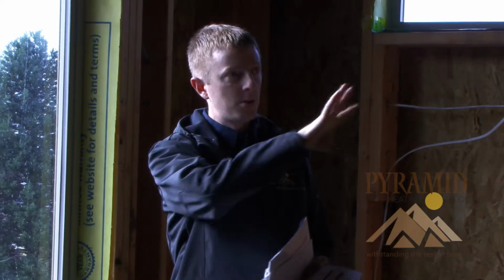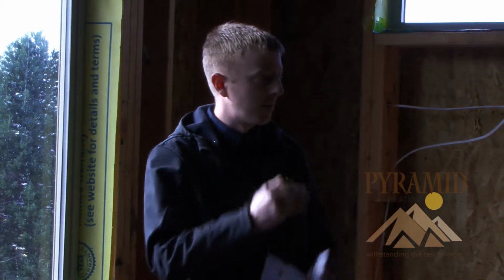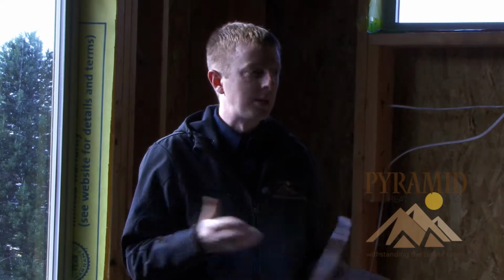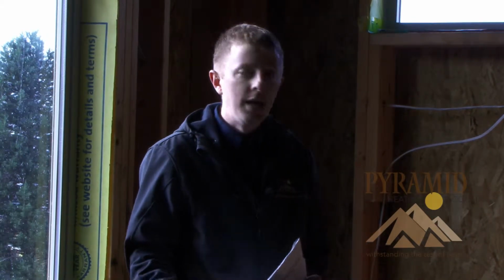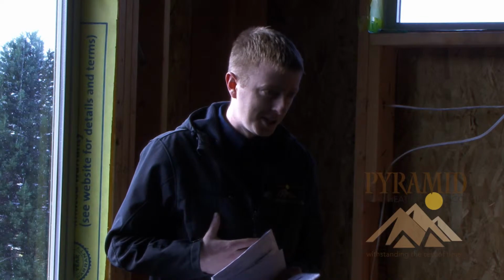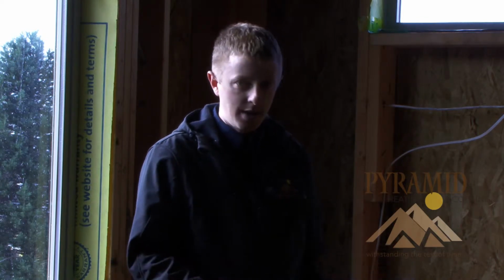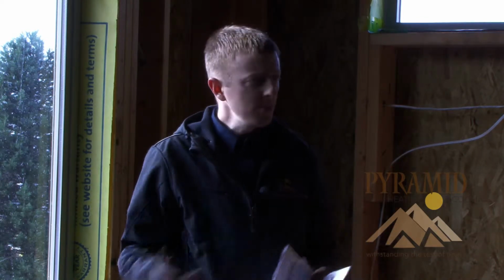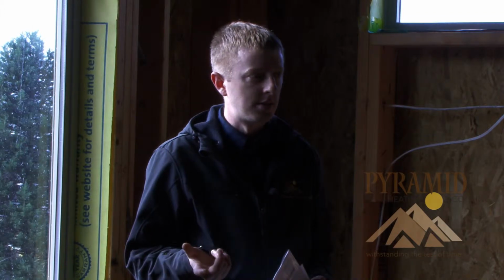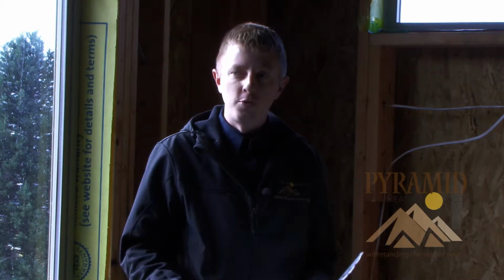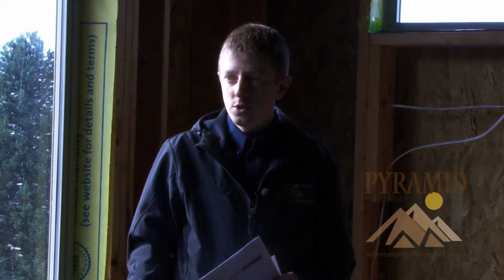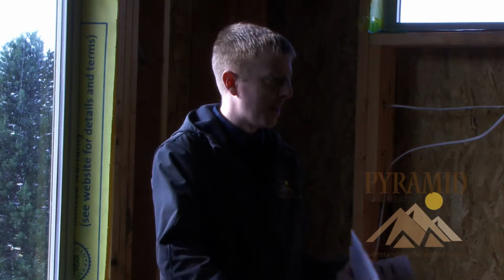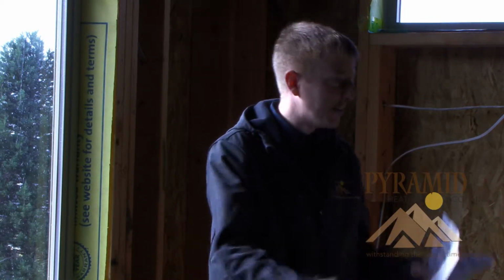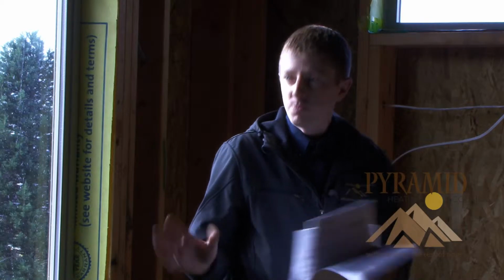So what we've done by putting the ductwork inside is you've now eliminated the ductwork being different temperatures in each location. It's much easier on us as heating guys to balance the house, because if your temperature is the same, the insulation and air sealing is the same, the upper floor and the lower floor perform the same. So you don't have a 72 degree downstairs and a 78 degree upstairs, which is fairly common.